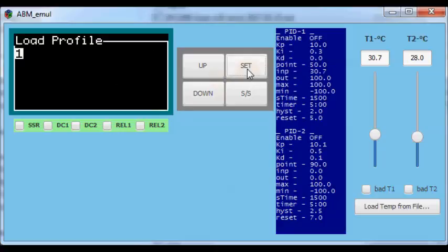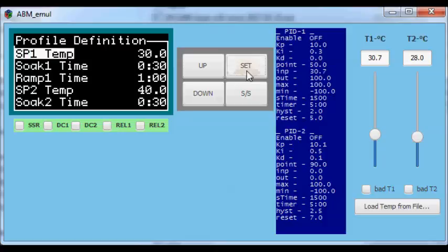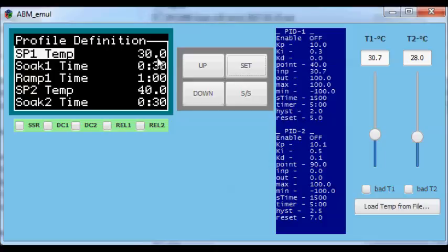I have already defined a profile, so let's see how it is built. Profiles have an index from 1 to 10. You can load profile 1 and see its construction. Each profile is made up of a setpoint temperature and a soak time — the soak time is the time where the temperature is constant — while the ramp time is the time to go from one setpoint to another. In this case we start from 30 degrees at setpoint 1 and keep this temperature for 30 seconds.